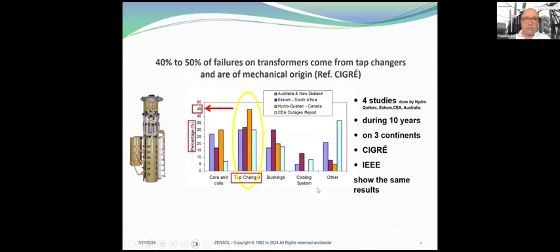40% to 50% of failures on transformers come from tap changers and are of mechanical origin. Four studies done by Hydro-Quebec, the Canadian Electricity Association, and also in Australia, during 10 years on 3 continents, and confirmed by Cigre and IEEE, show exactly the same results. If you see here in orange, Hydro-Quebec has close to 45% of failures coming from the tap changers.